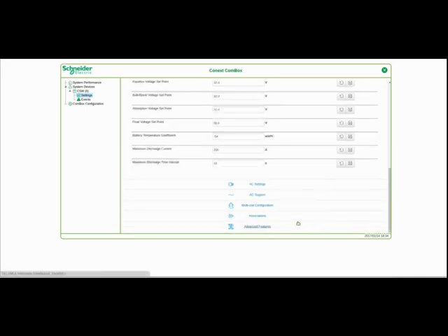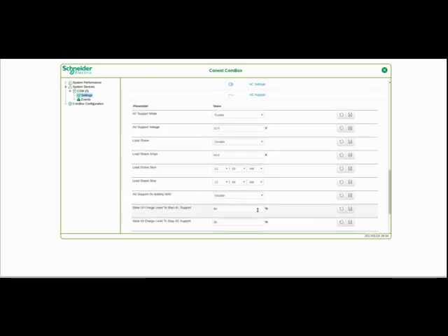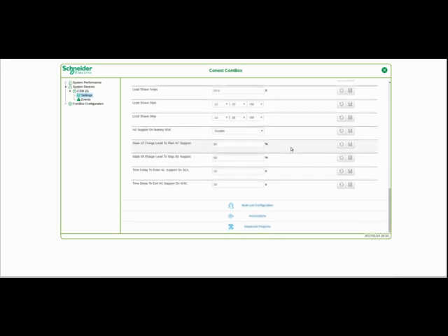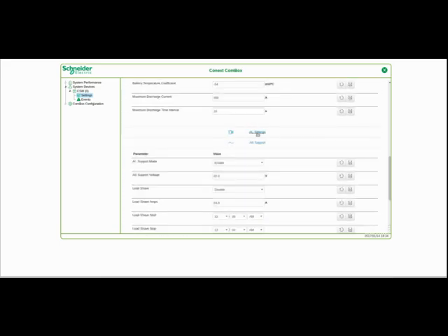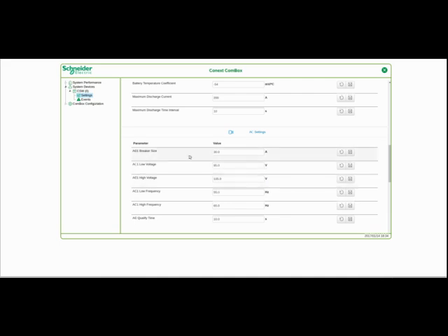It also gives me a lot of additional support, like AC support mode, which is what you saw as far as grid support. There are also additional AC settings: I can set the breaker size, and tell it what I consider low voltage and high voltage in terms of qualifying the signal.